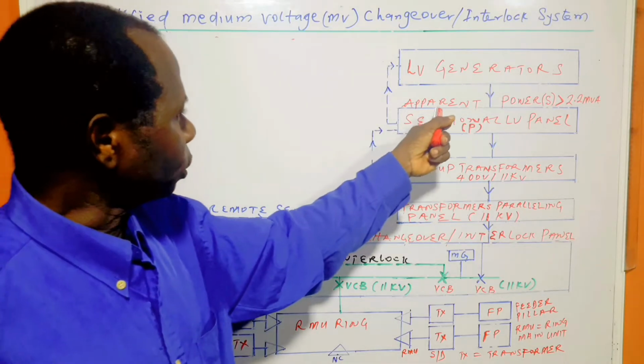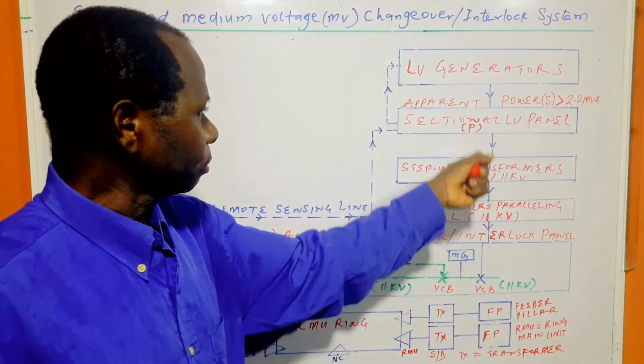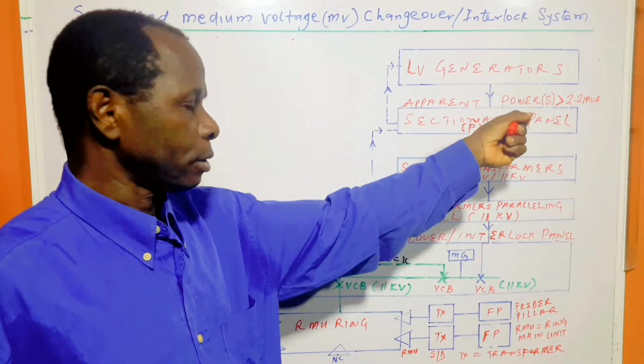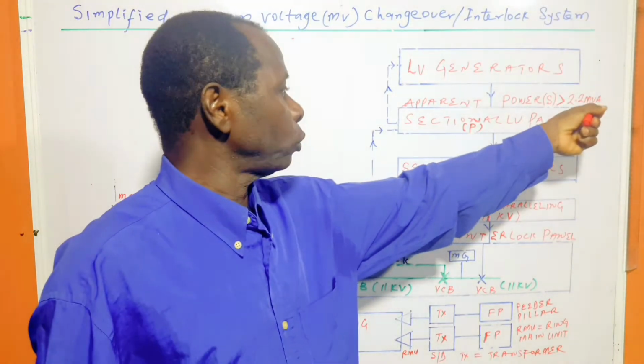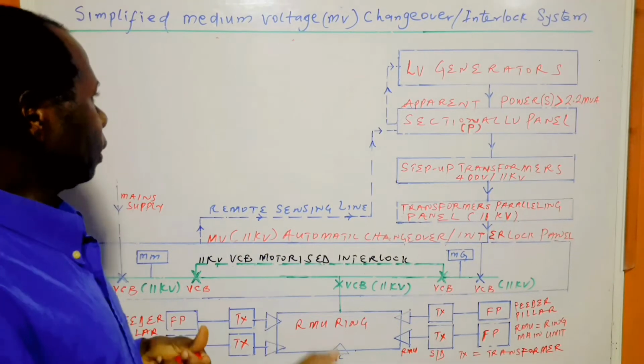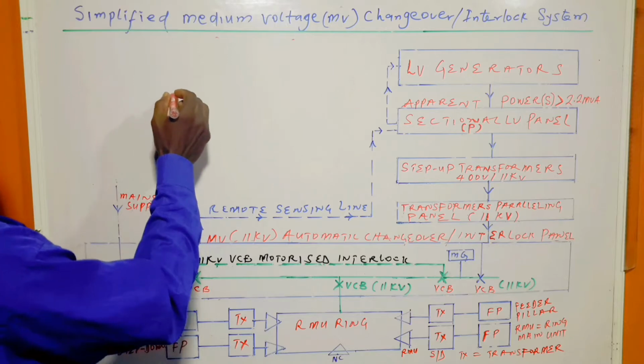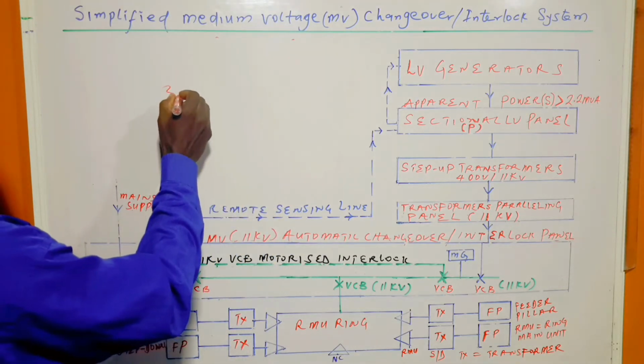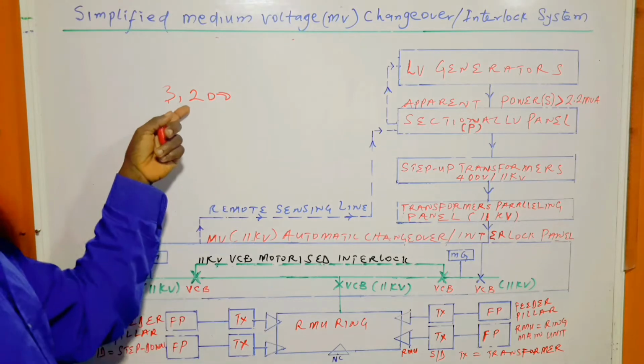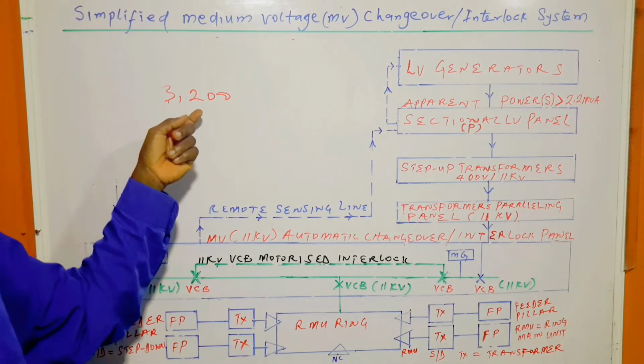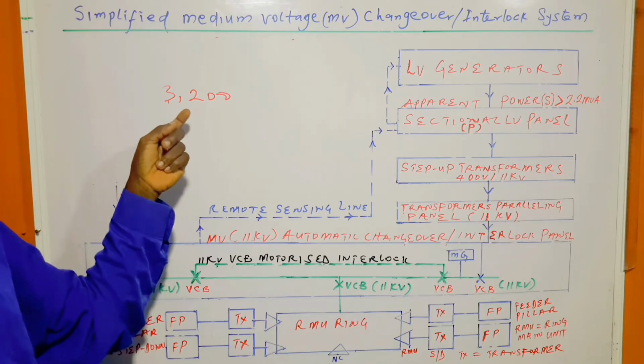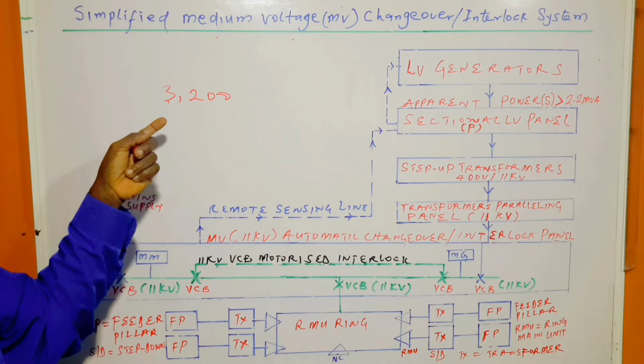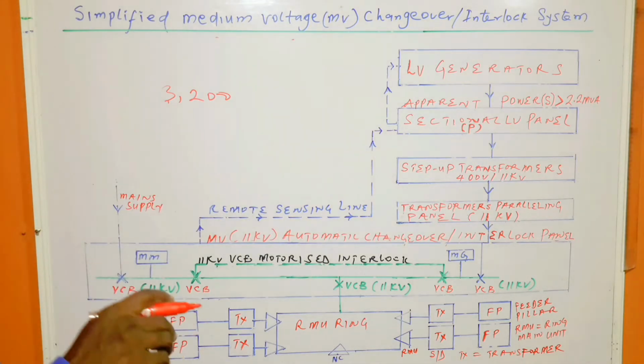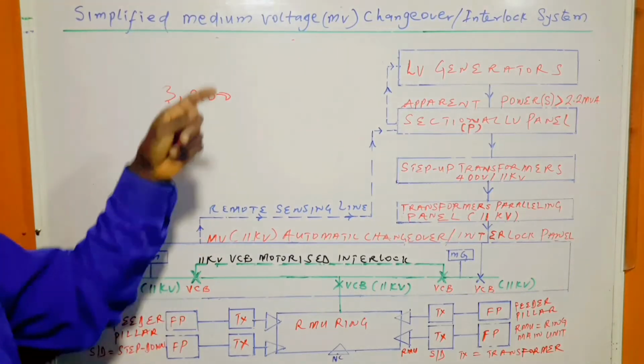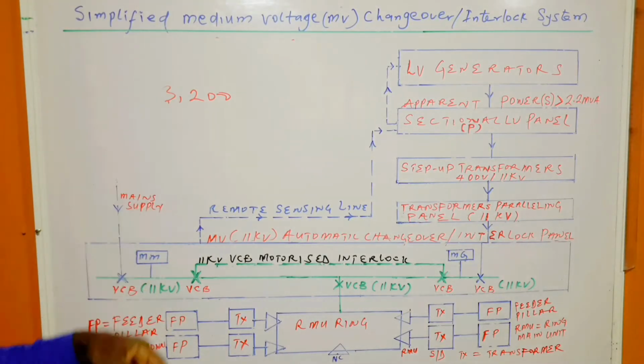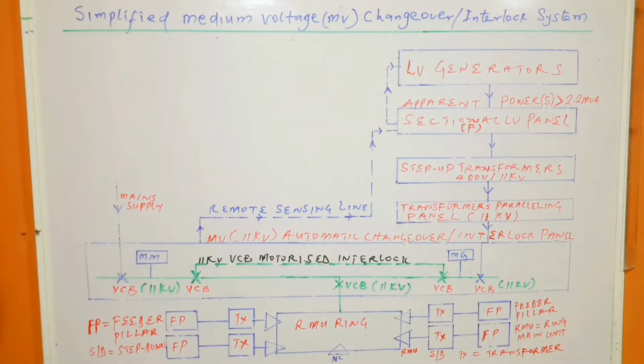Then we come to this: this system is designed for power requirement greater than 2.2 MVA. Because if it is greater than 2.2 MVA, then the LV current will be more than 3200 A, which is the rating of the biggest MCCB that can be readily found in the market. Since it is greater than what this one can cope with, we have to step it up, and that is what brings in the use of medium voltage, which is 11 kV in this situation.